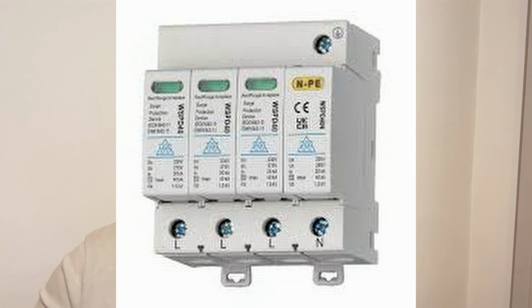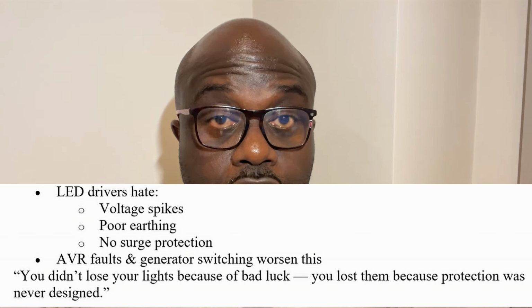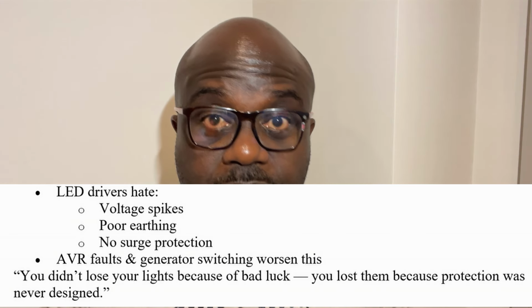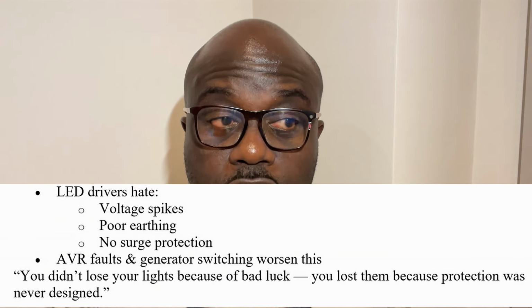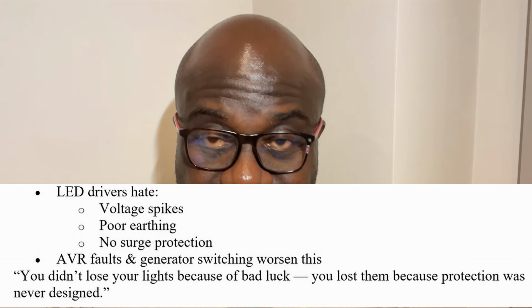LED drivers hate, number 1, voltage spikes. They hate poor earthing. They hate surges. So if you don't have surge protection, know that you're risking your LED light fittings being damaged or stopping working after a while. An AVR fault or generator switching can worsen this. You don't lose your lights because of bad luck. You lost them because protection was never designed.